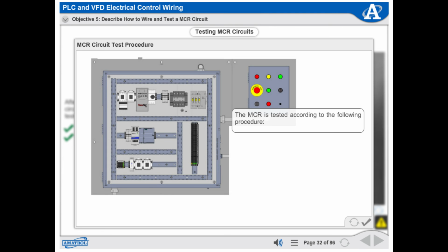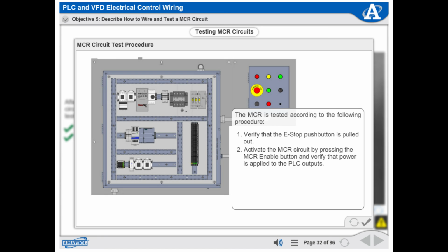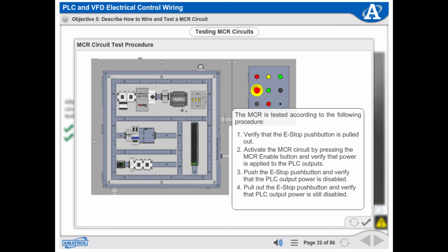The master control relay is tested according to the following procedure. Verify that the E-stop push button is pulled out. Activate the master control relay circuit by pressing the master control relay enable button and verify that power is applied to the PLC outputs. Push the E-stop push button and verify that the PLC output power is disabled. Pull out the E-stop push button and verify that PLC output power is still disabled. And repeat step 2.